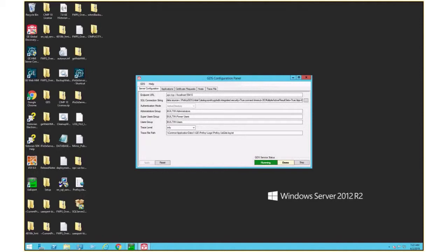Another question in the chat window. With multiple brands of devices, do you need to use multiple OPC servers? No. With this one OPC UA server running, if multiple clients connect, it's totally supported. It creates a different session for each client, and that one UA server continues to handle those multiple connections.